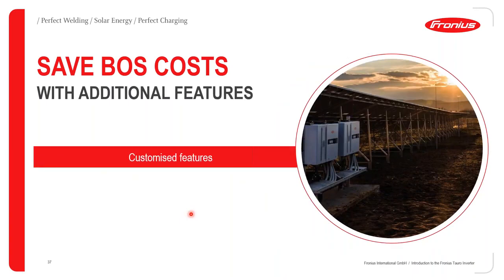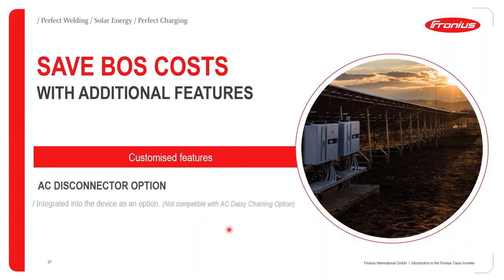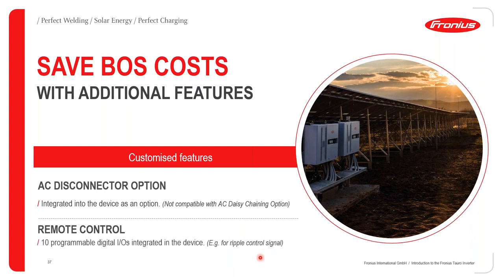In addition, we can also do customization for you. If you do require an AC disconnector, that can be integrated as an option. Once you choose to have this integrated into the inverter as an option, please take note that this is going to limit your ability to do AC daisy chaining with the Tauro inverters. Also, remote control is possible because the Tauro inverters have 10 programmable digital IOs, and this can assist you, just like with the other Fronius Snap inverters, to do a lot of controlling, even ripple control signals and stuff like that.